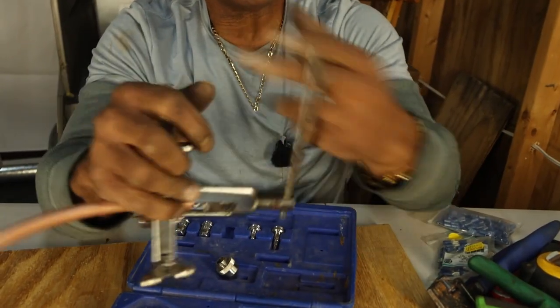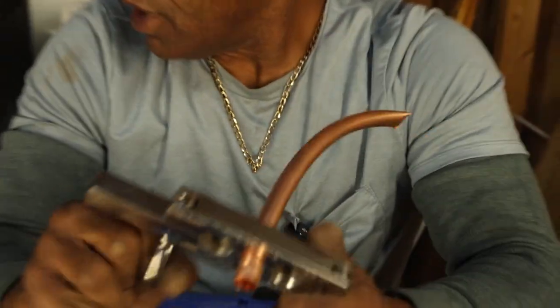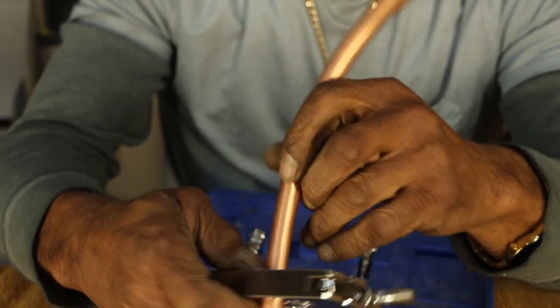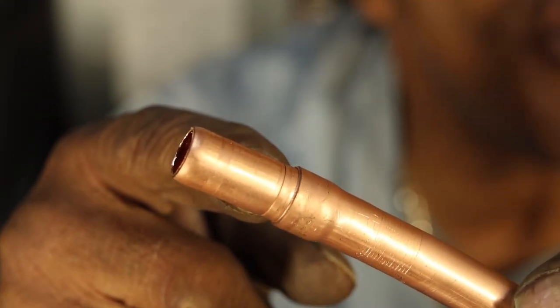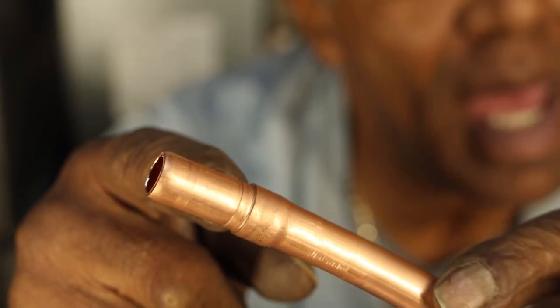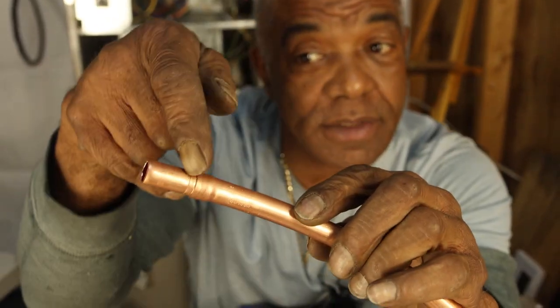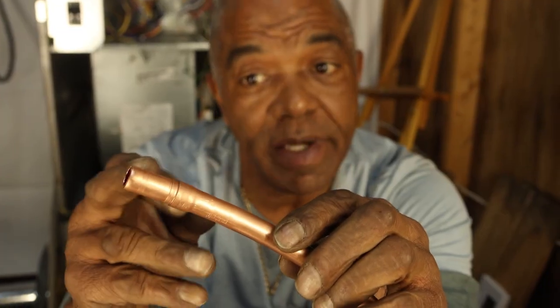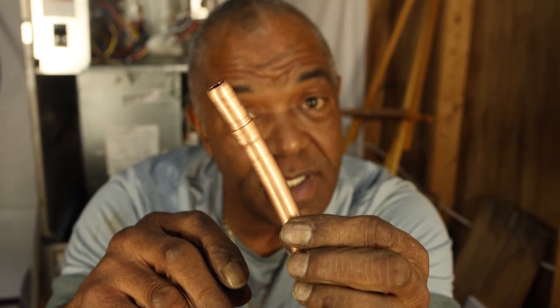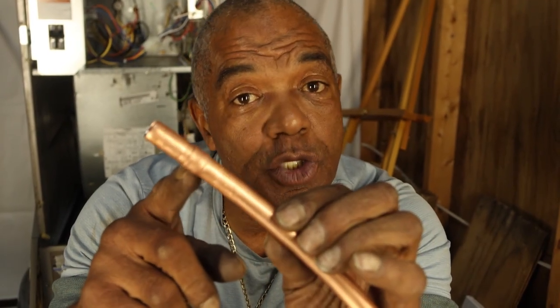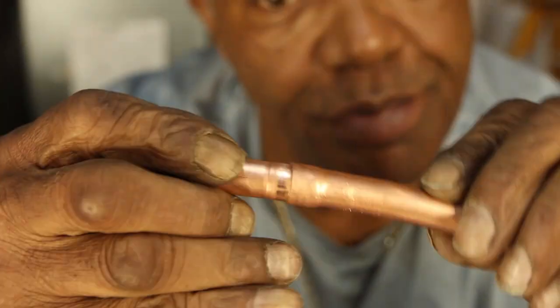now I can take another piece of copper of the same size. I can put it inside of itself. Boom. Now that copper is in this copper, and then I can use a torch and my brazing rod, which is a common method that we use for connecting copper. I can braze this with heat and brazing rod and make a permanent connection that will never leak Freon, will never leak. It'll be there for the life of the system. One method of connecting our copper is to swedge, stick the same size copper inside of itself and braze it.